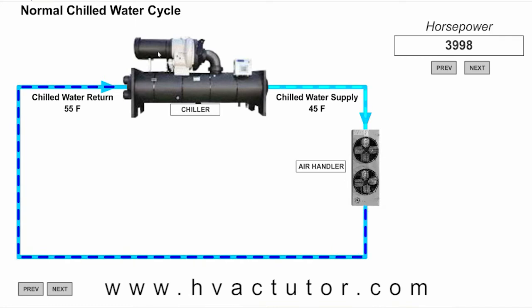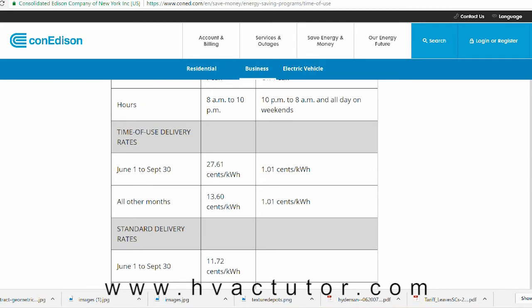Usually our rule of thumb is 1 horsepower per ton of cooling. 4,000 horsepower is going to be roughly 3,000 kilowatts. Now this is where it starts to get interesting. During the peak hours from 8 a.m. to 10 p.m., during the months of June 1st to September 30th, it's 27 cents per kilowatt hour. During the off-peak hours, 10 p.m. to 8 a.m., it is 1 cent.